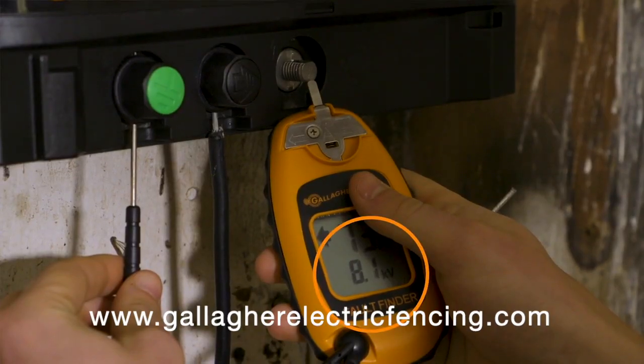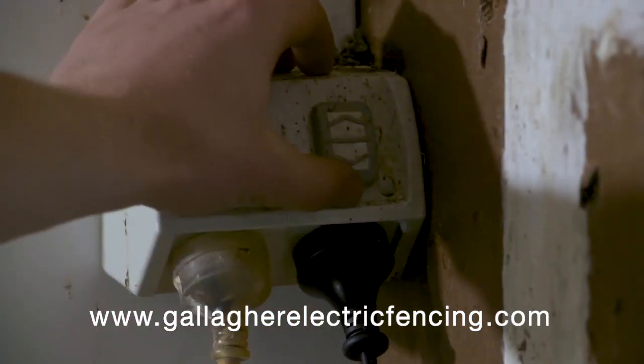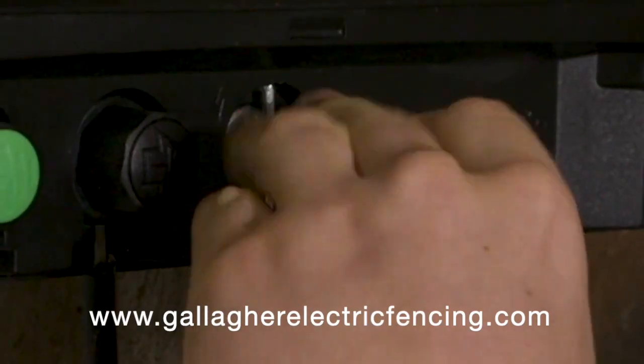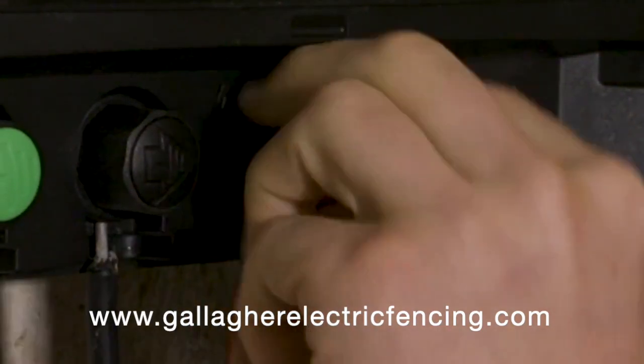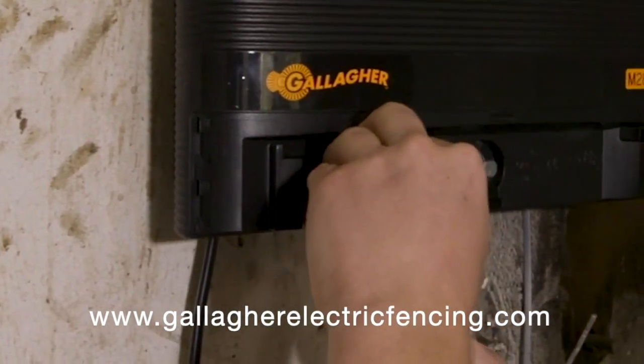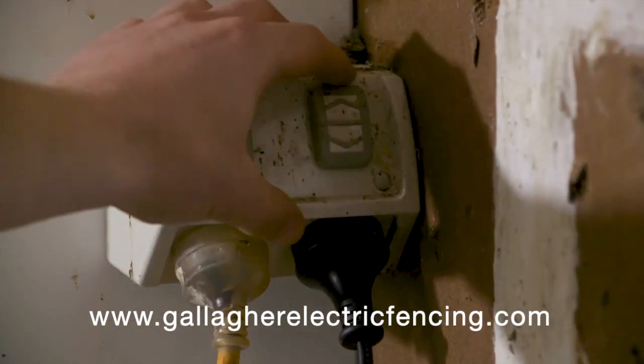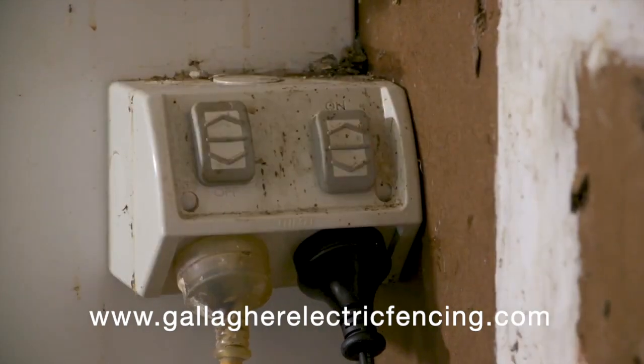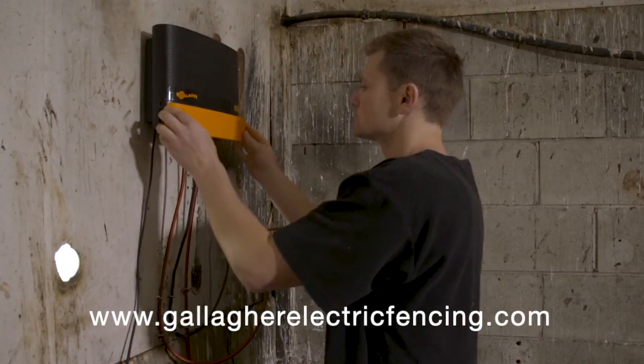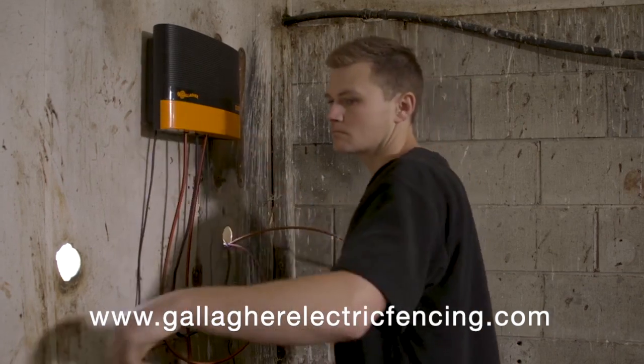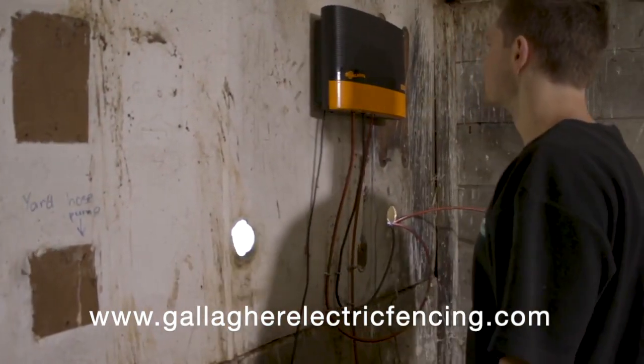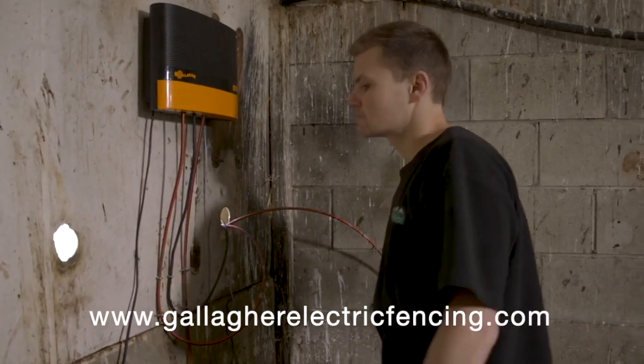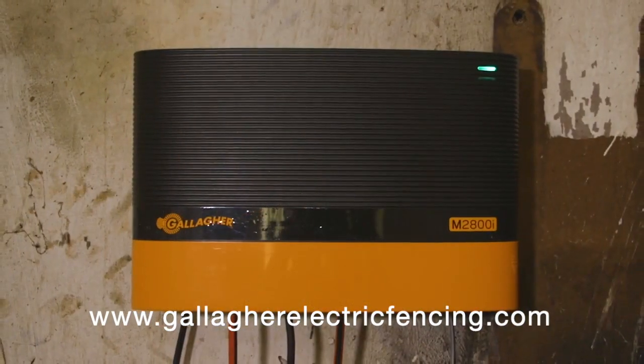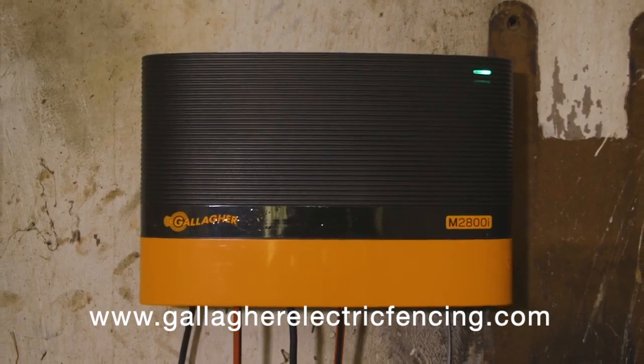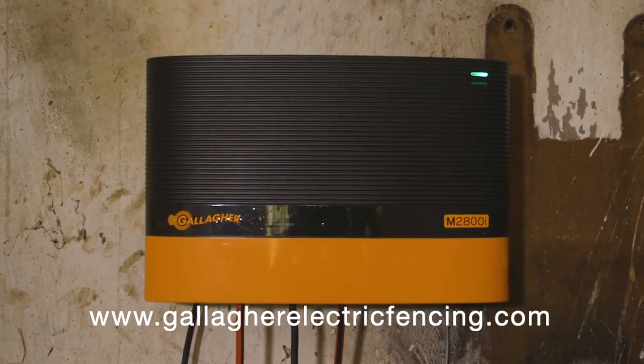If the voltage reading is over 5,000 volts, then your energizer is working as expected. Turn the energizer off again and reconnect the fence lead-out cable to the red terminal knob and the ground cable to the green terminal knob. Then turn the energizer on. If there is no voltage, check there is power at the power source. Once you have established the power source is working and there is still little or no voltage, then the problem is with your energizer. You'll need to take your energizer back to your Gallagher dealer for further testing.